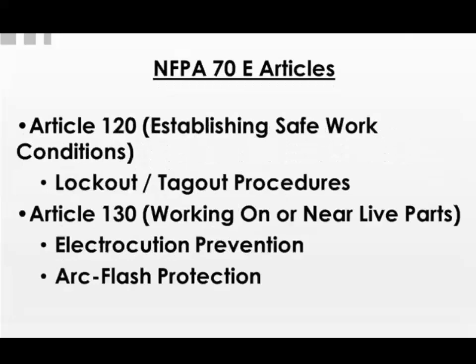NFPA 70E, Article 120, talks about requirements for establishing safe work conditions. Obviously, this falls under electrically safe work practices. So OSHA requires a lockout tagout program, or lock, tag, try, as it's now often called, or tryout. The try being the verification of energy isolation before a piece of equipment is worked on. So before any piece of equipment is worked on, ideally, if at all possible, it should be de-energized.